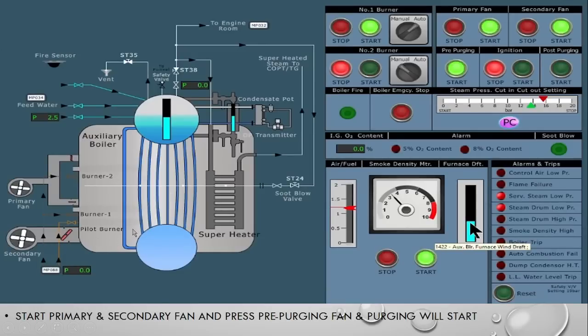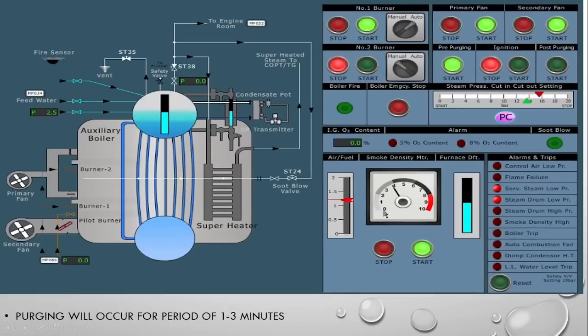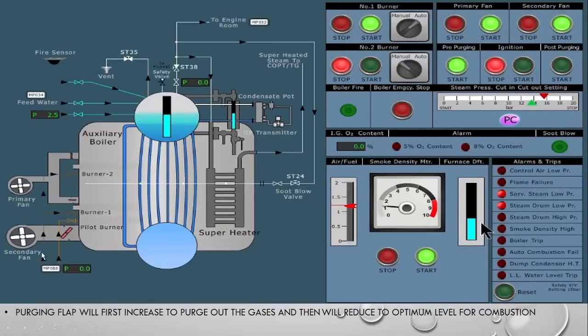What is happening during pre-purging: more air is being sent inside the boiler to forcefully remove any unburned or uncombustible gases present from the last combustion. We do this to ensure that when combustion starts, the air inside is clean, in optimum amount, and all uncombustible gases and carbon from the last combustion are removed. Pre-purging takes place mainly for a period of one to three minutes depending on the type of boiler. The smoke density will go up and then come back down. After pre-purging, the purging flap will return to optimum condition for ignition.